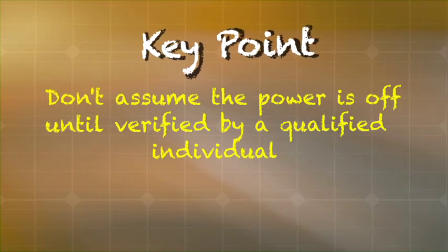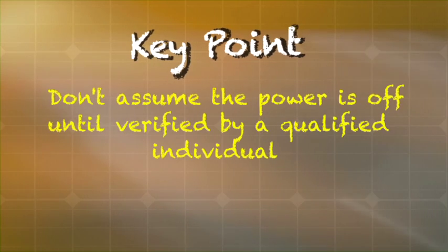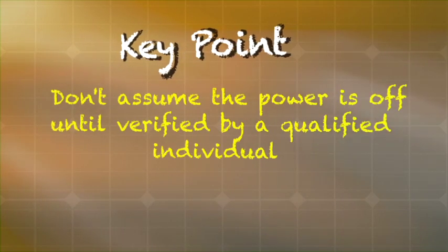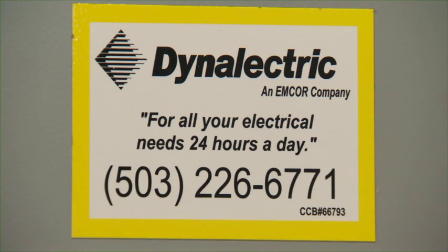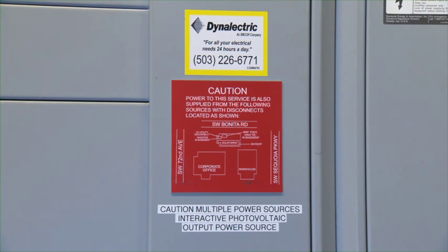Don't assume the power's off until it's verified by a qualified individual. Unfortunately, you can't call the utility—who we have to call is people like Nick, the local contractors in our area. Hopefully there's a sticker on the inverter that says installed by a solar company, with an 800 number and 24-hour response. Just because somebody's an electrician doesn't mean they know solar; it's oftentimes the opposite, because DC is very different.